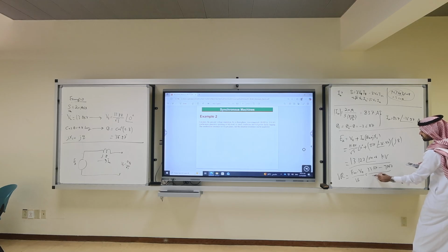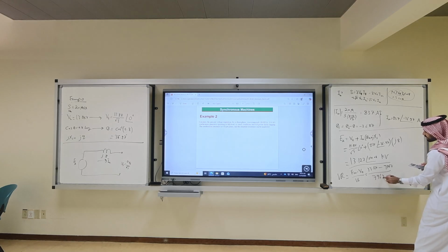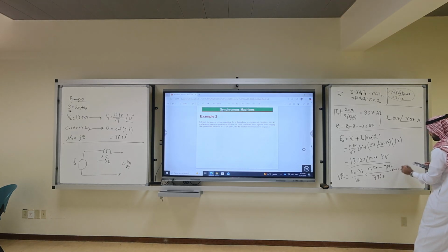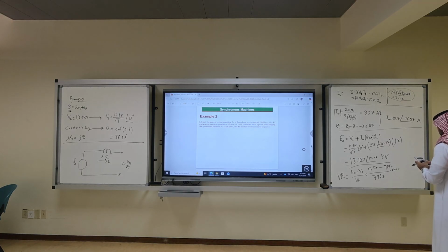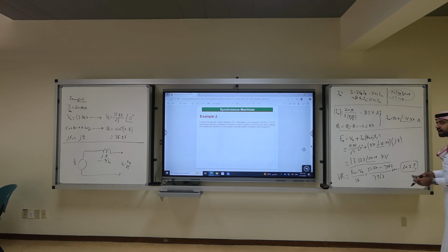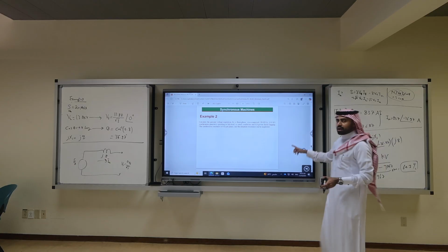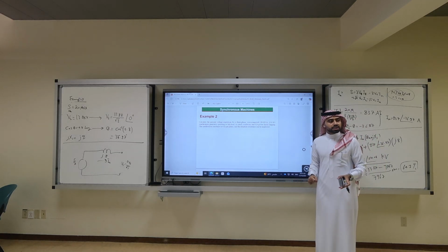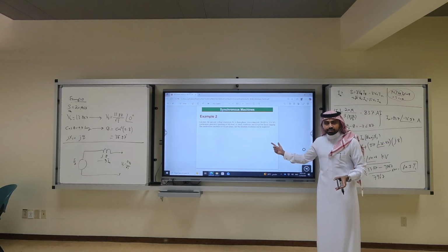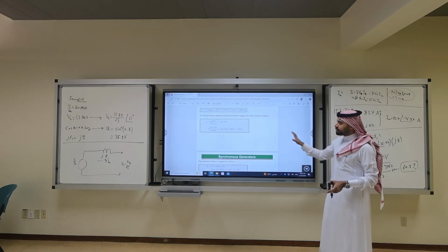7,967, over 7,967, multiplied by 100. So 13,127 minus 7,967, over 7,967, multiplied by 100. That's maybe 64.7%. Is this a big VR or a small VR? Big VR. So this is overexcited. Clear? I hope you understand this example.